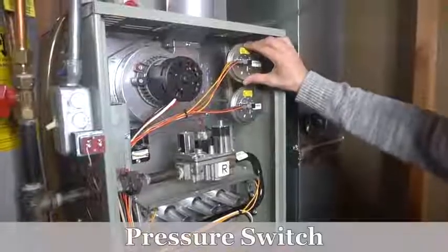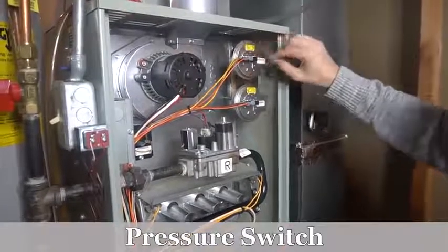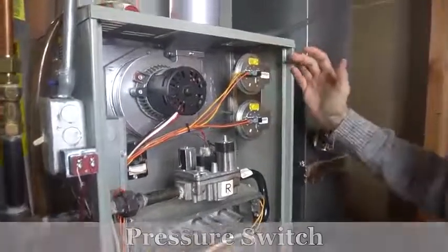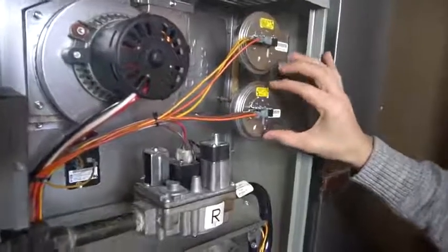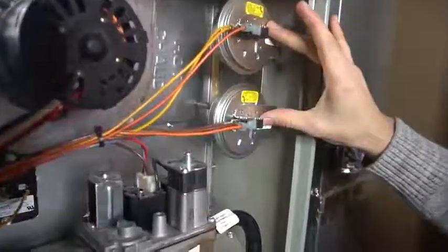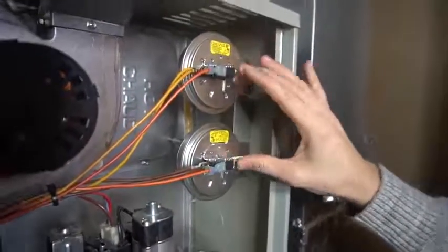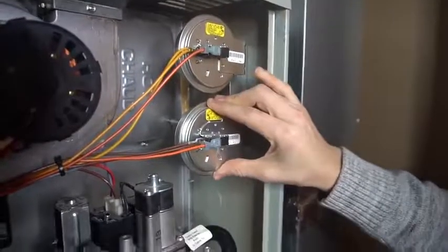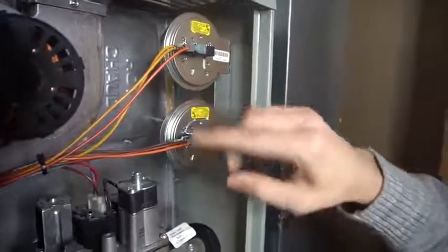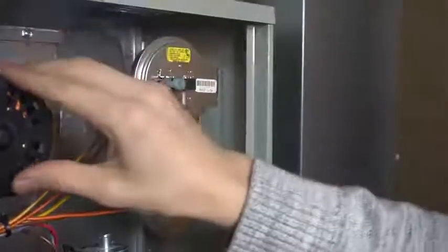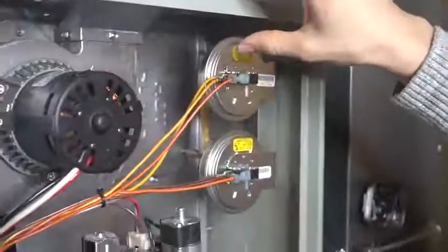And right here we have a pressure switch. Pressure switches are usually going to be round, like you see on mine. They can be plastic or metal. Sometimes they're going to be a lot smaller than this one. I have two, once again, because I have a two-stage furnace. The purpose of the pressure switch is to prove that we have an adequate draft, or in other words, that my inducer motor is exhausting the combustion gases properly.